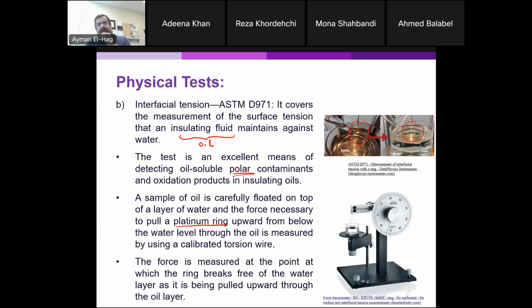I want to add something here. This test is considered a very difficult test, and it's not easy to conduct and needs some special people with special skills to be able to do that and understand what is going on. And this is why one of the projects I assigned to you is to predict the IFT, the interfacial tension. Why? Because it's a very hard test to do, as you can see here, compared to other tests, as we will see, like for example, water content or breakdown voltage or acidity. These are relatively much easier tests to be done. So if we can predict this value, which is, in my opinion, one of the very critical tests in transformer oil, it can reveal a lot of things about it.